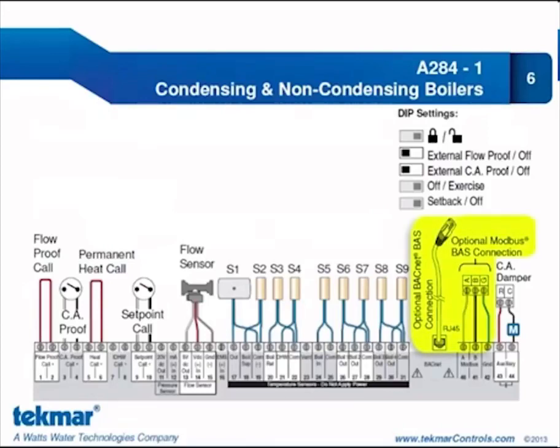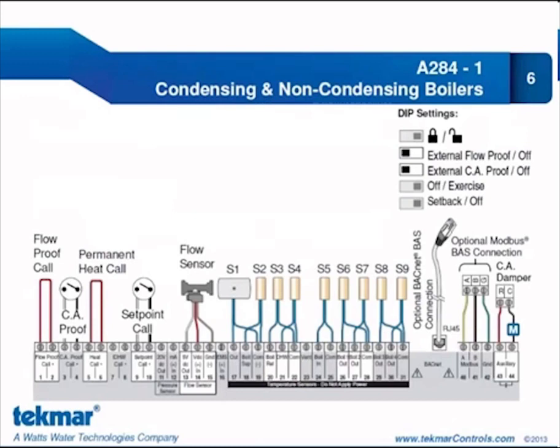For communication terminals, since we are communicating to a building automation system using either BACnet or Modbus, we've shown both connections. The BACnet connection is through an RJ45 port at the top of the 284, and the Modbus connection comes through terminals 40, 41, and 42. You'll also see the auxiliary relay, which in this case is being used to control the combustion air damper. This relay can be used to control either a combustion air damper or a recirculation pump for domestic hot water applications.